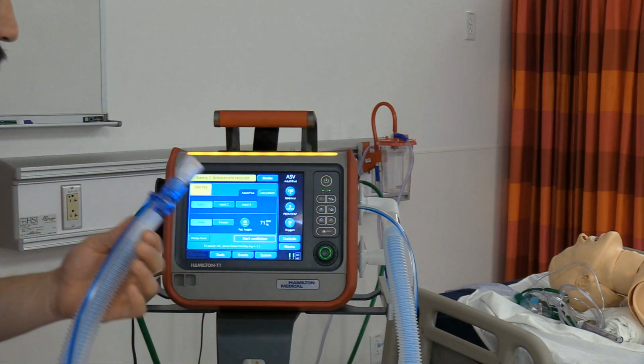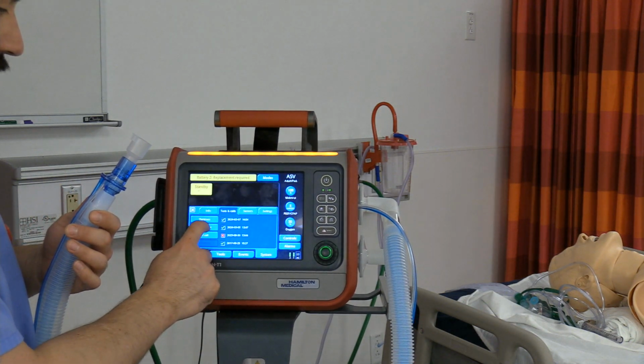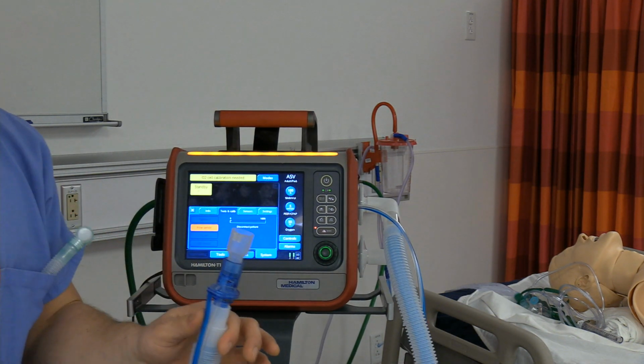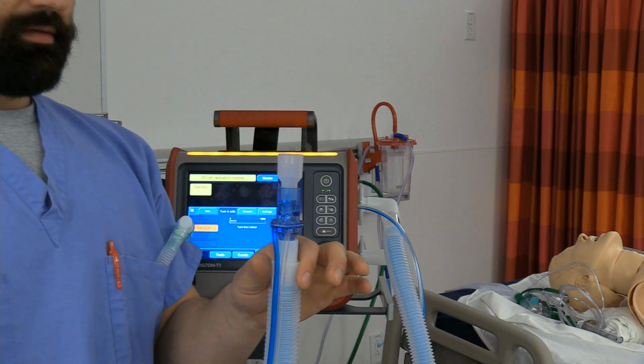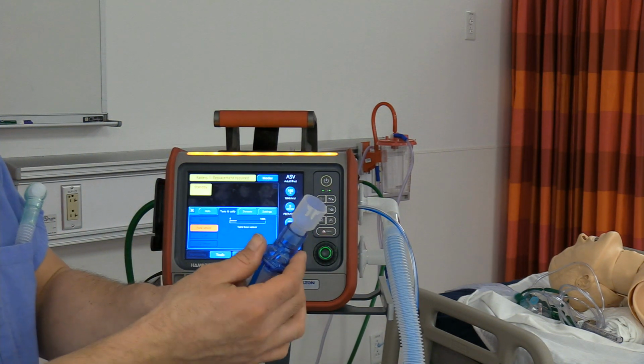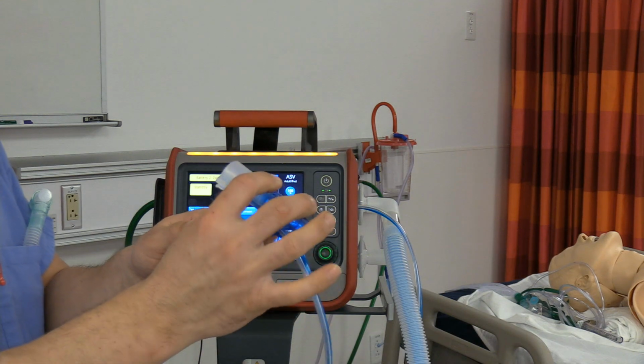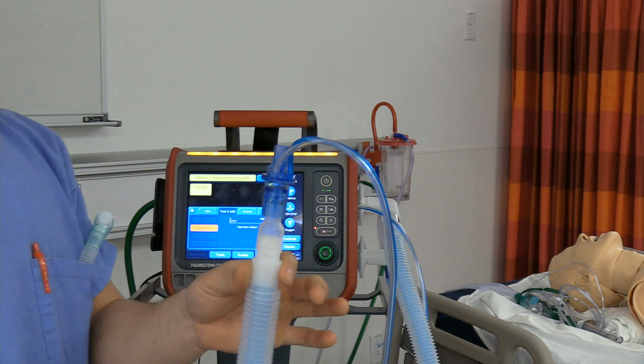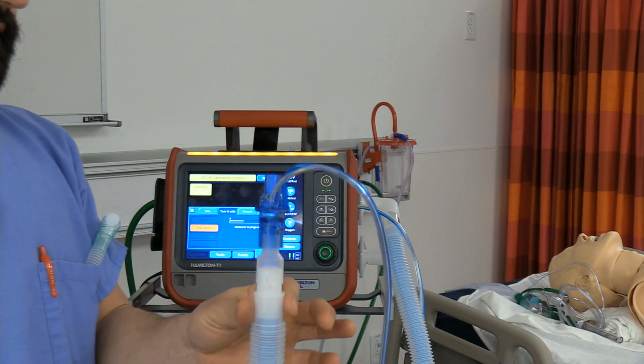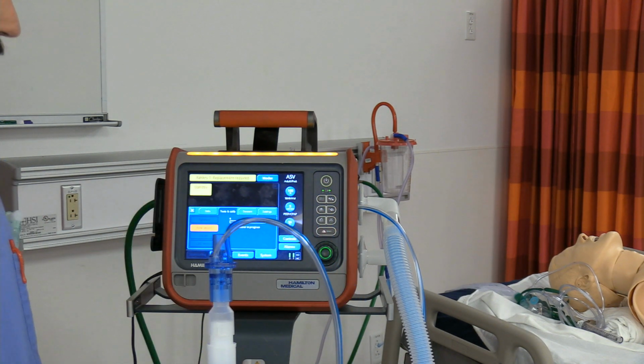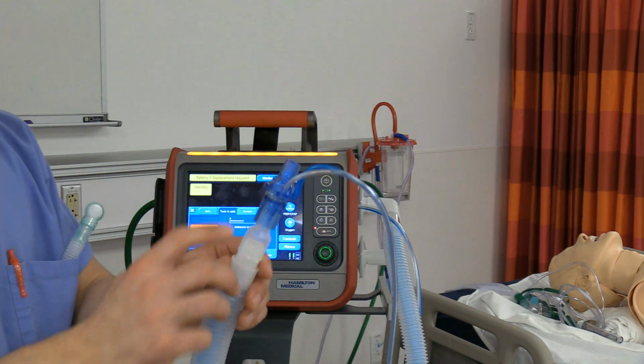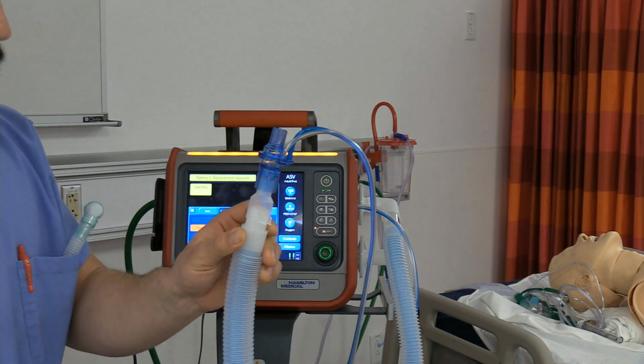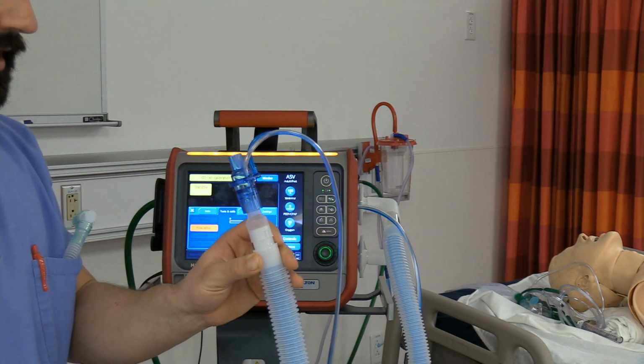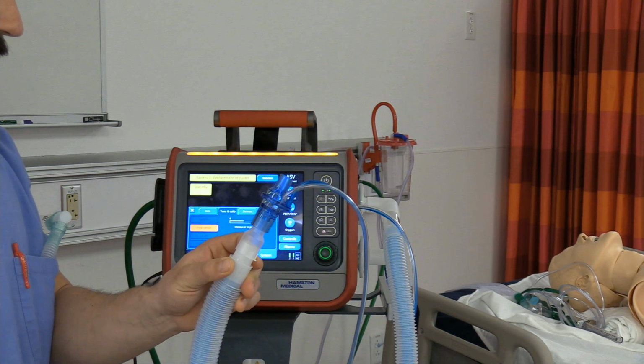So you can typically start with this piece on. So I'm going to go ahead and go to pre-op check. Flow sensor. It's going to tell me disconnect patient. Once again, this is not ventilating my patient. It's telling me turn flow sensor. That's where if I already have this piece on, it allows me to swiftly turn. If I'm too slow with this, it is going to just jump me out. If you look really, really closely, you can see these little materials moving on the inside, almost imperceptible to the naked eye.